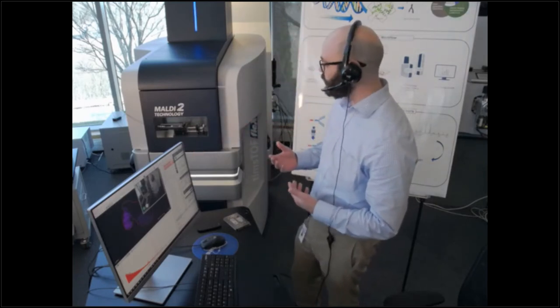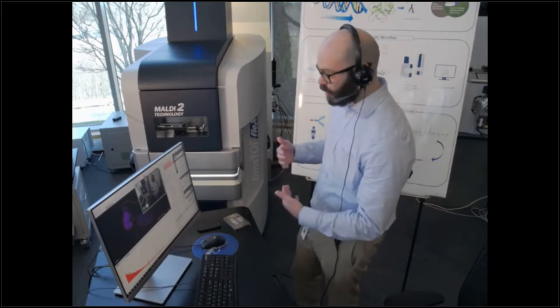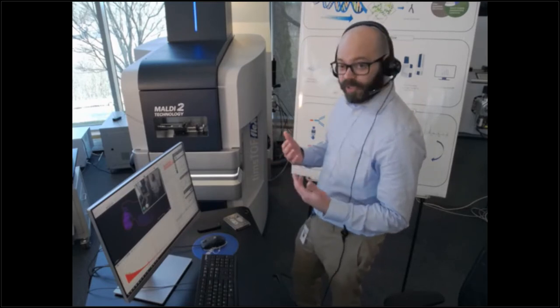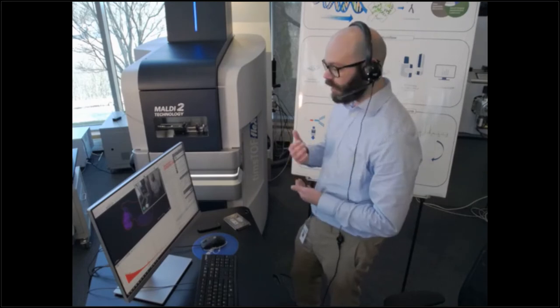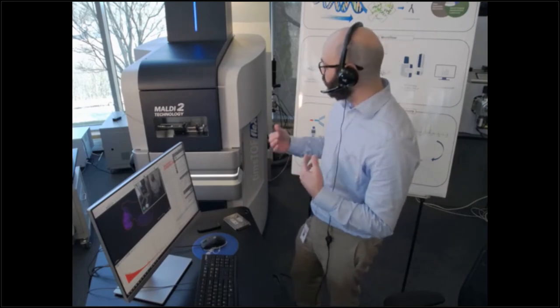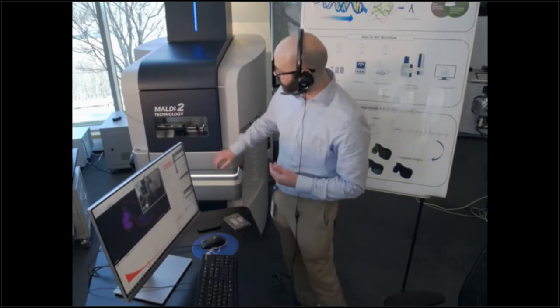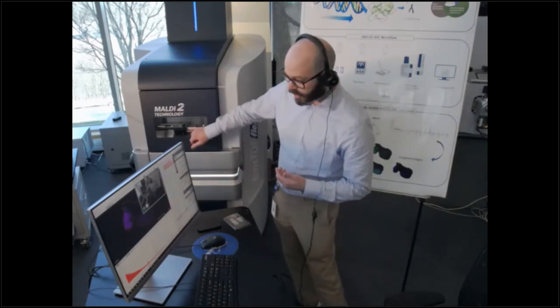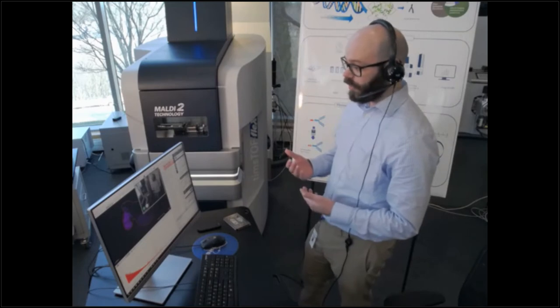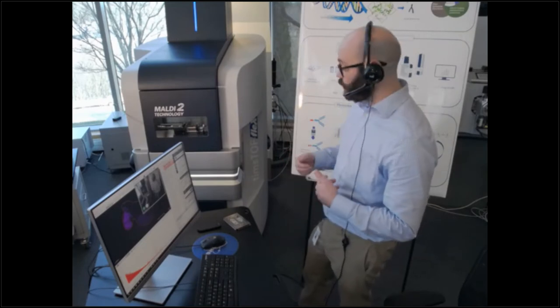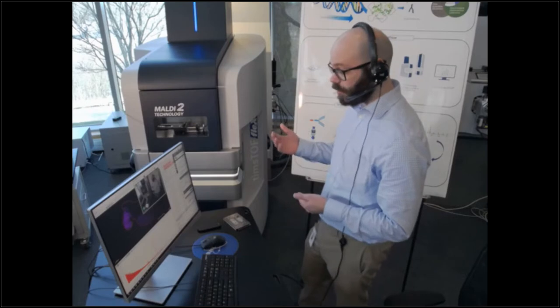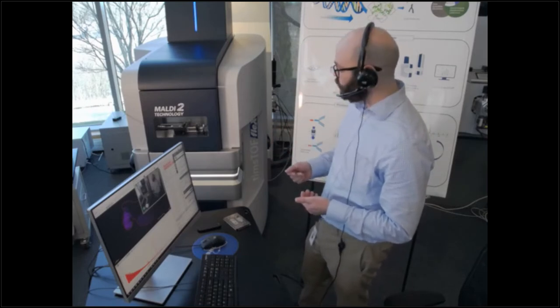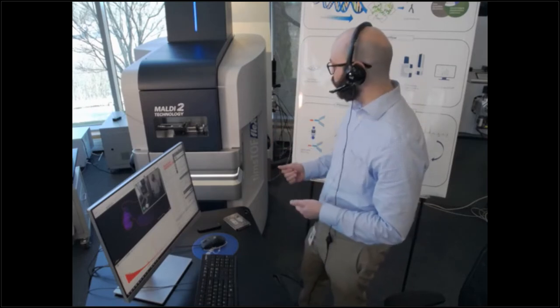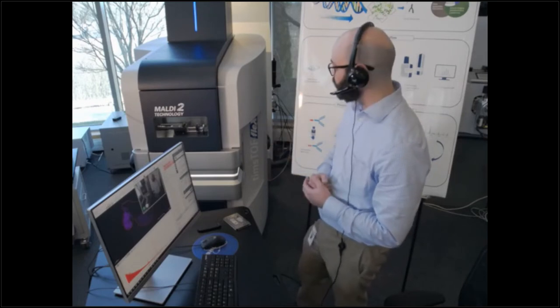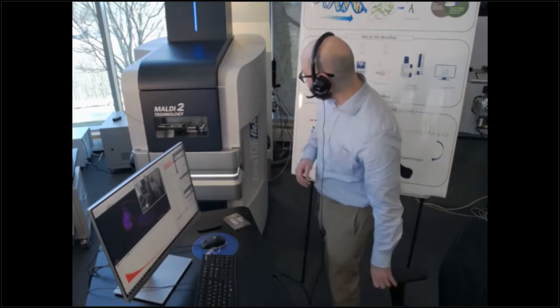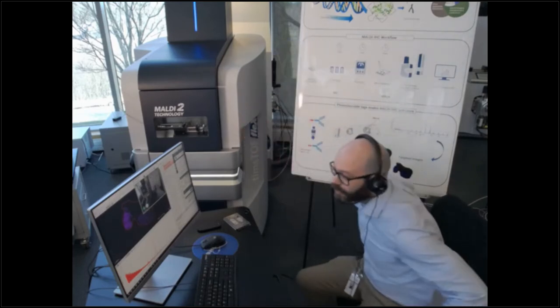What's really neat is these sources both interface in the same region at the same pressure, so it makes switching back and forth between MALDI and ESI very fast and very easy. I'll demonstrate that a little bit later in the program. The last thing I want to show you is below this MALDI II technology logo, we have a syringe loaded with calibrant. That way we can do our mass calibrations, and if you're using TIMS, which we aren't today, you can do your TIMS calibrations by switching quickly to the ESI source. You can calibrate, then switch right back to MALDI, and we'll do that actual workflow in real time in a second here. Okay, so I think that's all that I wanted to show for the instrument.